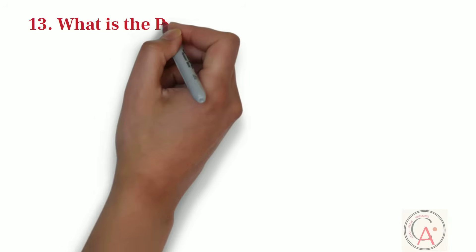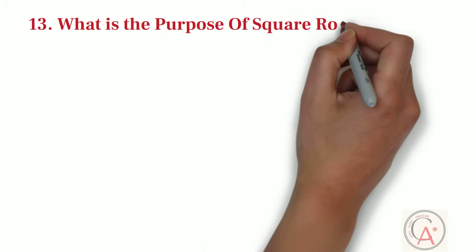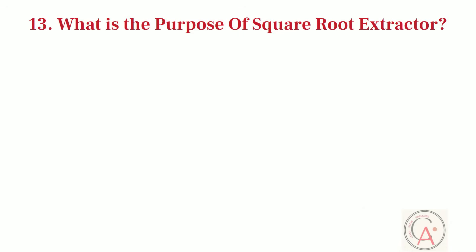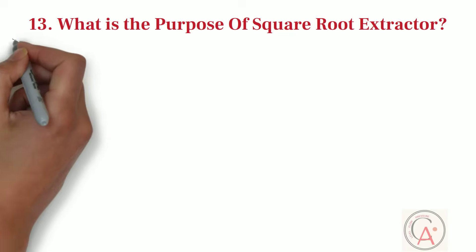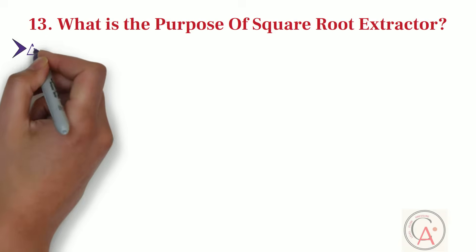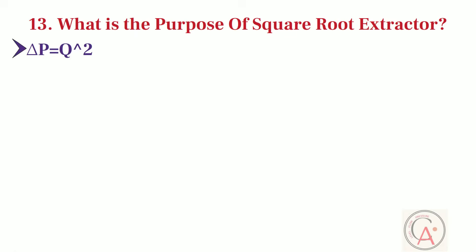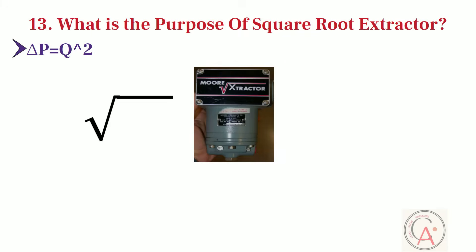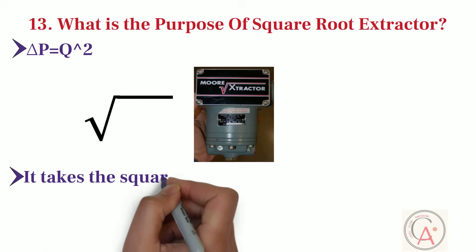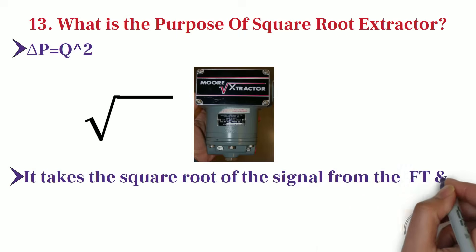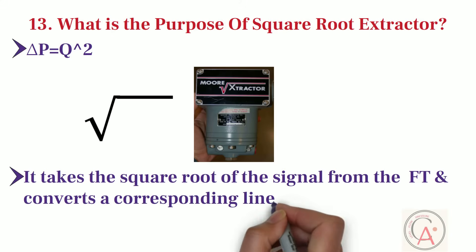One of the most important and basic technical question is, what is the purpose of square root extractor in DPT? As we know that differential pressure developed by a venturi, orifice plate, pitot tube, or any other acceleration-based flow element is proportional to the square of the flow rate. Square root extractor is a function or device which takes the square root of the signal from the flow transmitter and converts to corresponding linear flow signal.